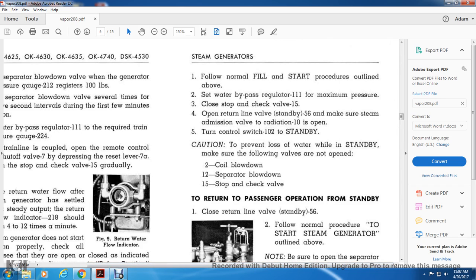1. Follow the normal fill and start procedures outlined. 2. Set the water bypass regulator 111 to the maximum pressure. 3. Close the stop and check valve 15. 4. Open the return line valve standby 56. Make sure the steam admission valve with the radiation 10 is open. 5. Turn the control switch 102 to standby.